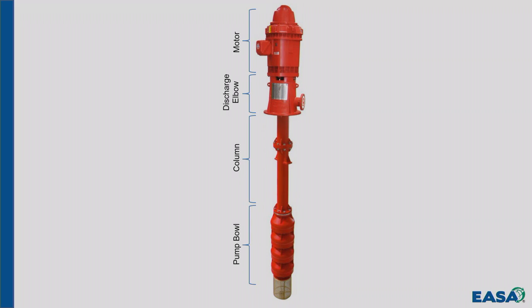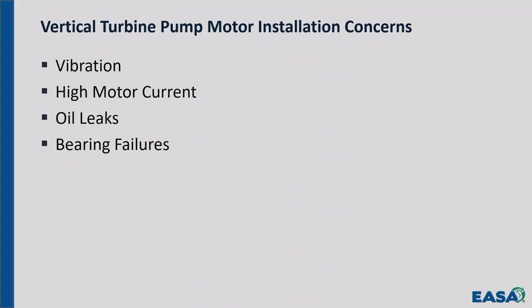Here are the areas that I've encountered as being problems when a vertical turbine pump motor is installed, and I get a phone call saying there's an issue. The top one is vibration. Vibration is just a key issue with vertical turbine pumps and motors. So we're going to address some of those issues. Next, high motor current. The motor's pulling high current.